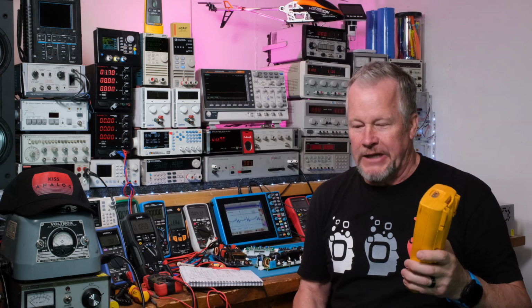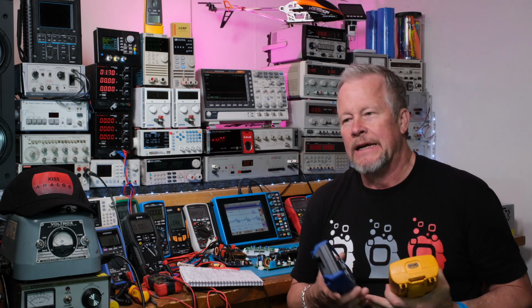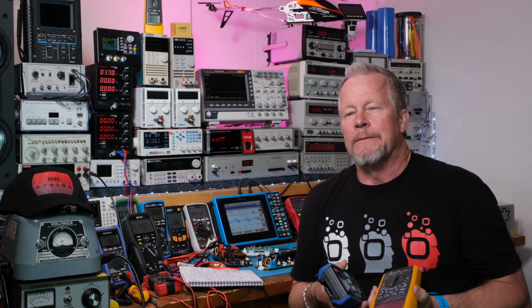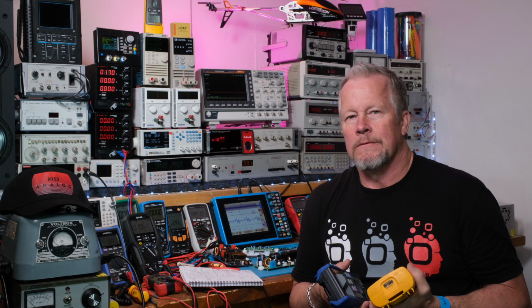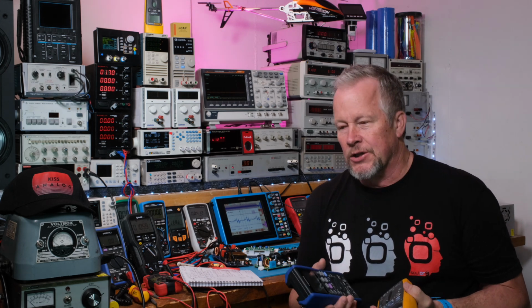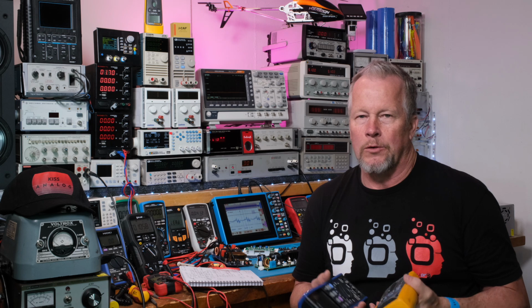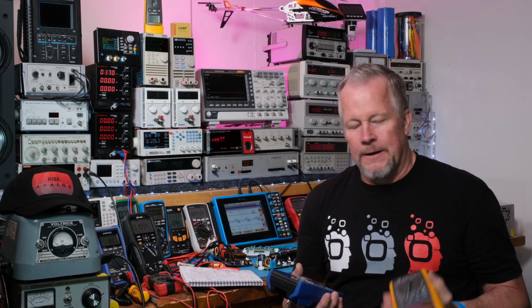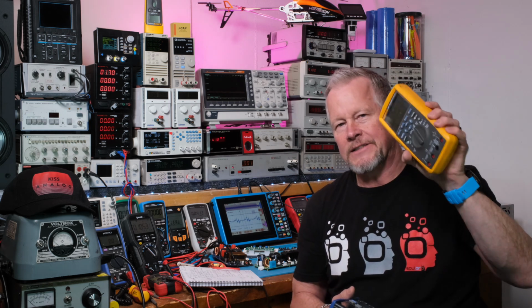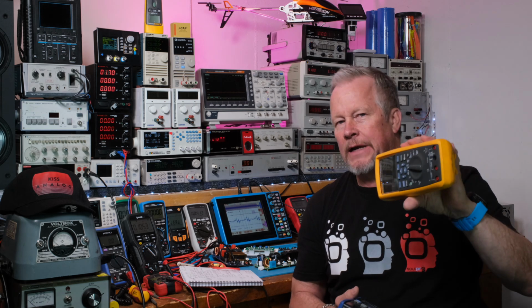So, you got the large count. The other thing is most meters, like the 6,000 count meters and 4,000, and even some of the higher count meters, are limited to 1 kilohertz bandwidth. So when you're reading AC voltages, or especially square waves that have all these harmonics going to higher frequencies, you may not get accurate measurements out towards 1K square waves. Sine waves you will, but after 1K, that falls off. So 100 kilohertz, that's awesome. For audio work, 100K is great.